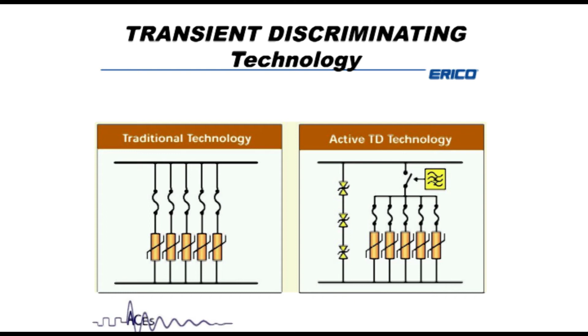So it's open circuit for 50 hertz. When we get an overvoltage, it's a short duration, it connects those MOVs into the circuit and limits that surge voltage. All we've done is improve the performance of the device by making sure it does nothing for 99.9% of the time. In that one moment where it's actually needed, it's ready to go. It hasn't been degraded by those overvoltages.